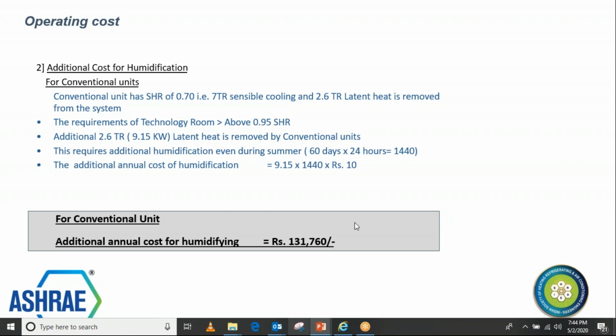Its compressor is trying to cool, and here you are humidifying, and also you are dehumidifying and humidifying. So this is happening because the conventional system works independently, and humidification, dehumidification, and heating cycles are not an integrated part of the conventional system. And this is in addition to whatever numbers are mentioned here. These numbers are mentioned only for the 2 months. So in 2 months, this is the latent capacity impact which is coming to the humidification.